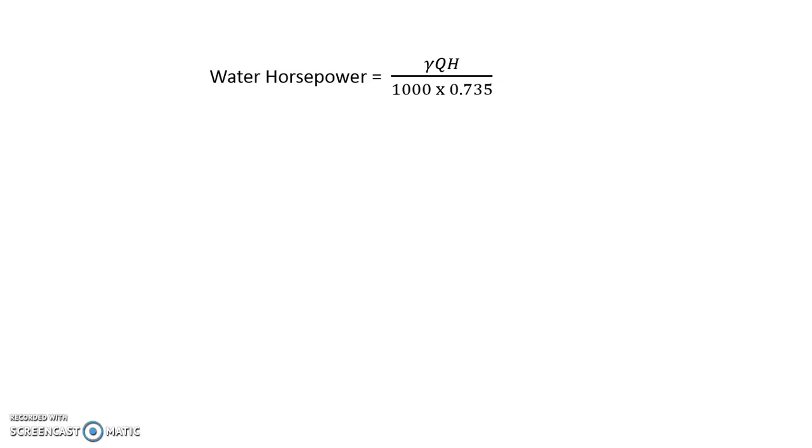Now what next? We'll calculate water horsepower. Water horsepower is γQH divided by 1000 × 0.735. Now here γQH by 1000 will yield the value in terms of kilowatts, divided by 0.735 will ultimately will give you the value in terms of horsepower. So it's around 29.62 horsepower by making the substitution for Q equals to the discharge, H is the total head, and γ for water is 9810 newton per meter cube.